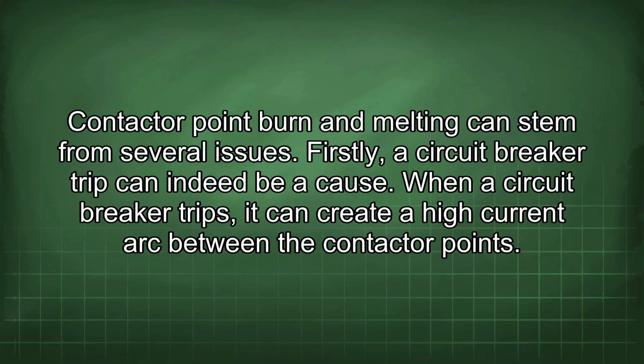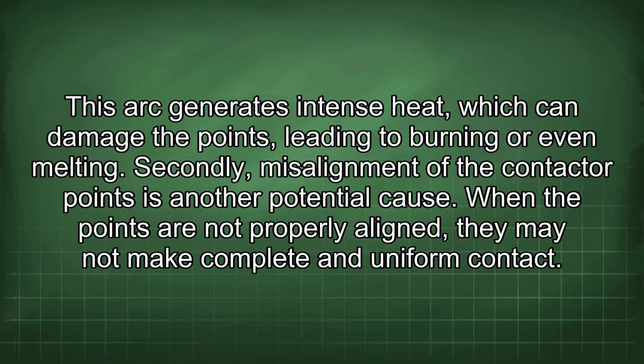Contactor point burn and melting can stem from several issues. Firstly, a circuit breaker trip can indeed be a cause. When a circuit breaker trips, it can create a high current arc between the contactor points. This arc generates intense heat, which can damage the points, leading to burning or even melting.